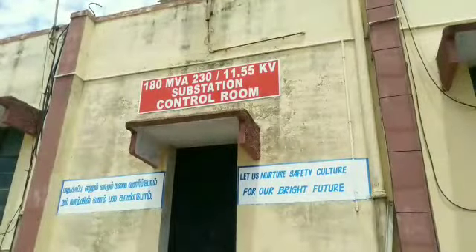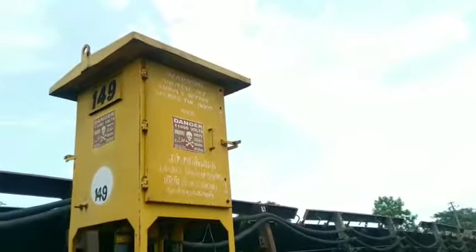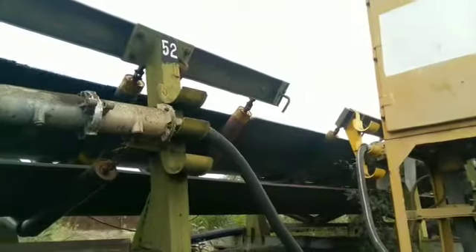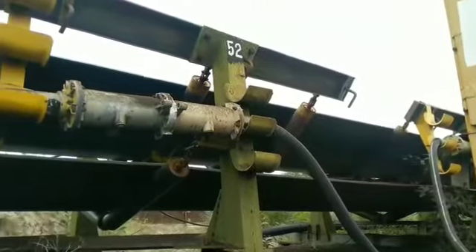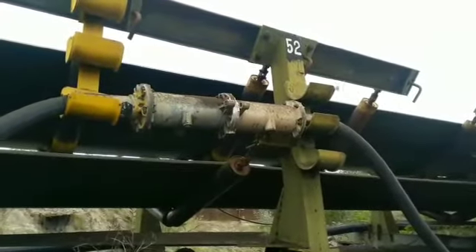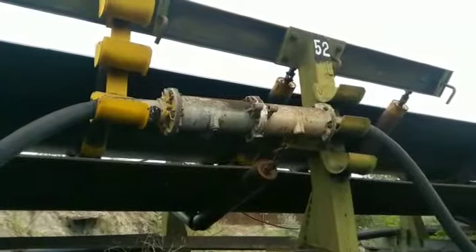From this substation, the electricity is supplied through landline cable via coupler and pillar box. The 11 kV cable length is only 1000 meters, so we use a coupler to connect between two cables, and the coupler should be placed in the coupler stand.